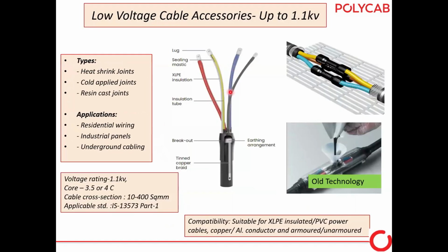Here I have shown the termination. That's a low voltage termination. This is the outdoor termination, indoor termination, and this is the joint. In olden days, or some of the customers still using this old technology, that's a resin cast joint. This resin cast joint has two disadvantages. One, this is not environment friendly. You cannot throw tin boxes of this resin cast joint in the open. You have to have a disposal plan for these joint boxes.